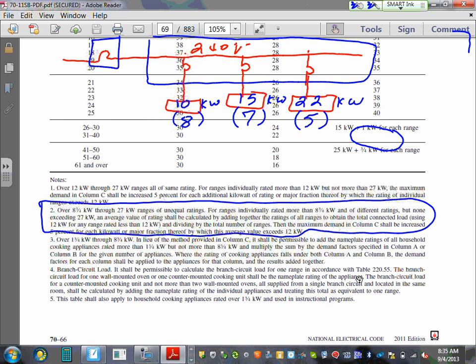One more time. If you guys read through this, it will tell you if the ranges that we have are over 8 3/4 through 27. Are we over 8 3/4 in size through 27? Yes, this applies directly to us. Step number 1: anything less than 12, make it 12. Did you hear me? Anything less than 12, make it 12. Then average them. Then increase the demand that you get for all of them under C by 5% for every kW more than 12. Let's go do that.